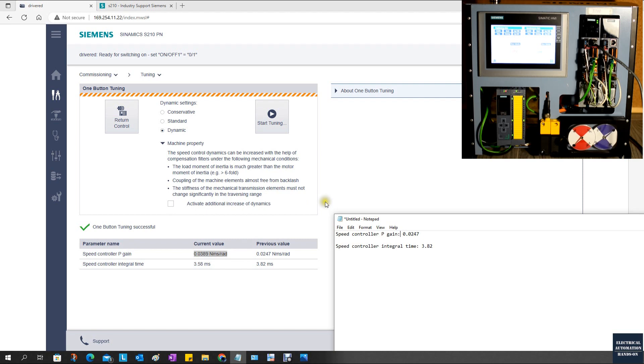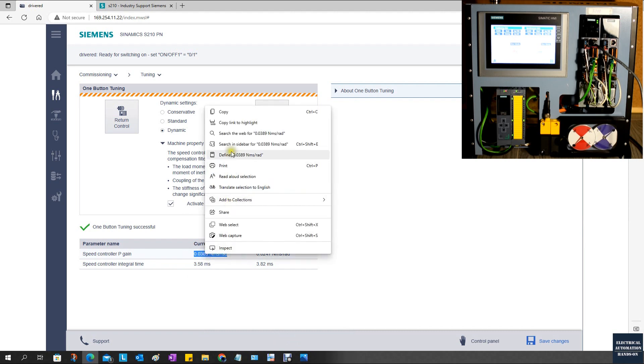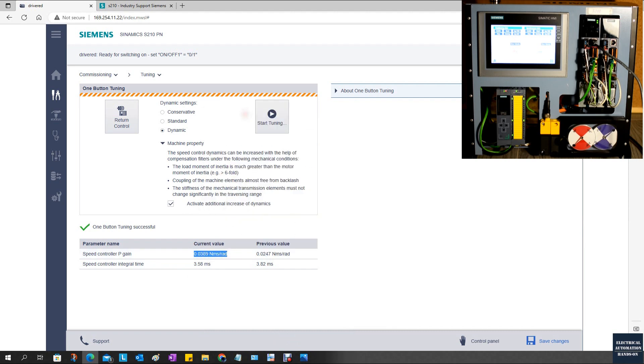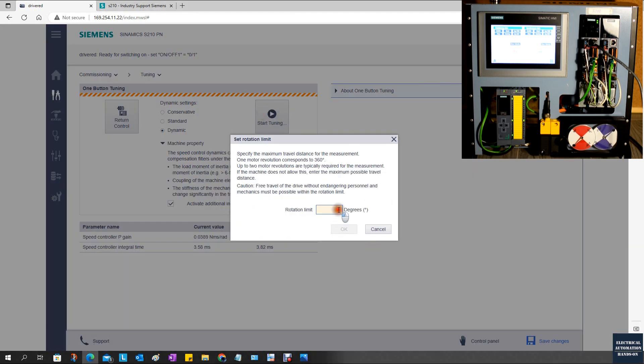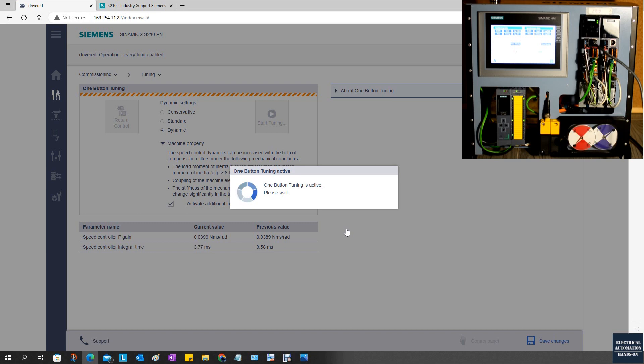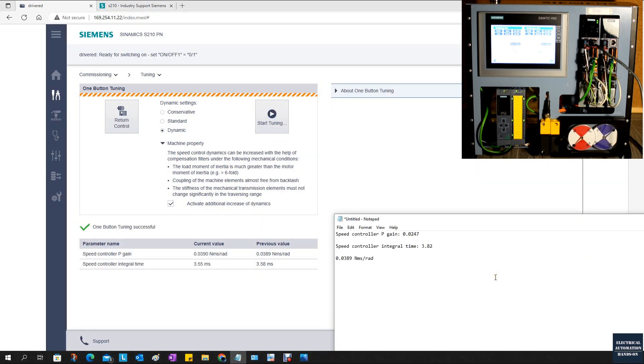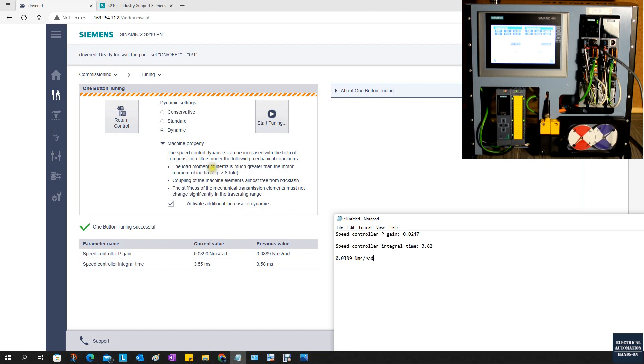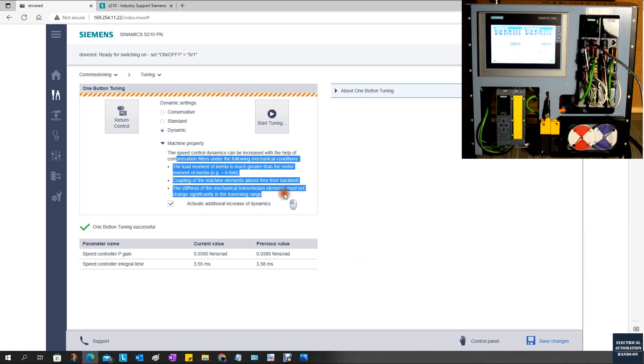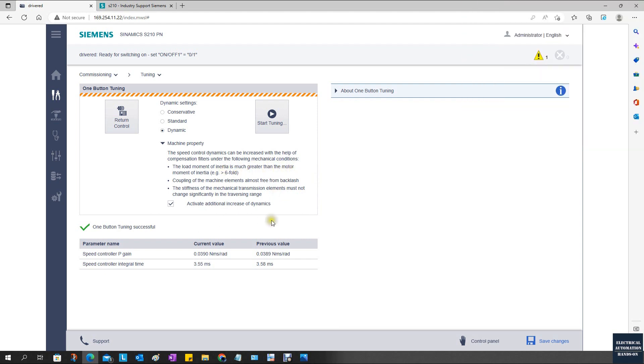We can also select this and see what's going on. I can also copy this. Now let's click tuning, same thing, and click OK. Let's compare. The P-gain does not increase too much. That's because, again, this load is too light, so it's not showing too much difference. But you need to carefully read this word. Basically, this free of backlash and also the inertia from your load.